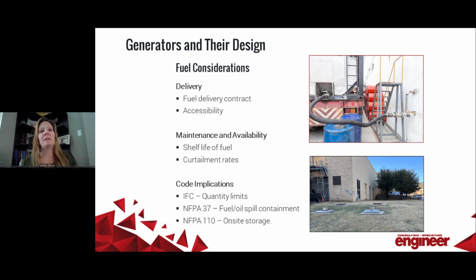So a curtailment rate allows a utility company to basically restrict the usage of fuel, which the boiler then would use the diesel fuel, eating into that required fuel storage. So taking that into account when you're calculating your runtime and your storage is definitely a requirement. And then, of course, with everything with engineering, there's more and more codes that reside when planning out the fuel system. Both the IBC and the IFC have storage quantity limits when you're dealing with indoor fuel. Specifically, IBC Table 307 limits that storage of Type 2 diesel to only 120 gallons inside of a control area.